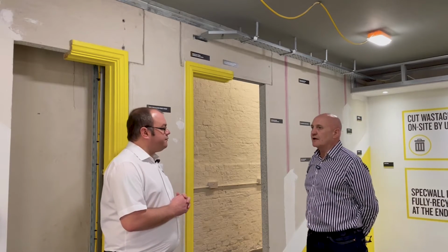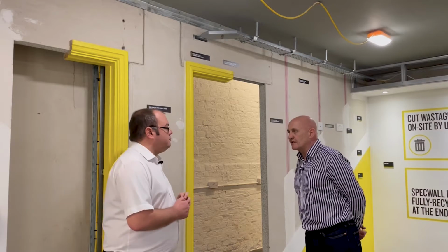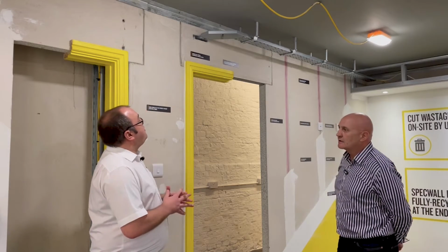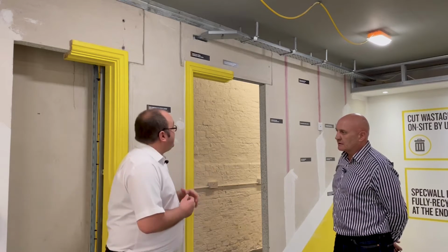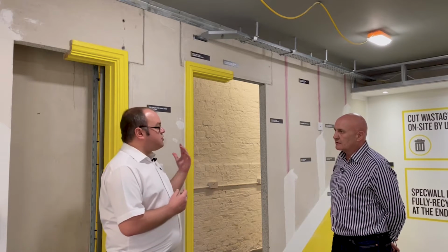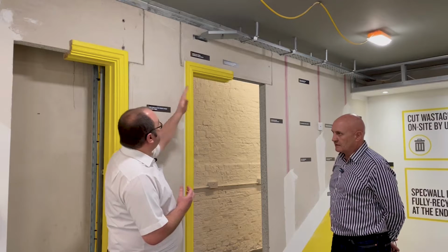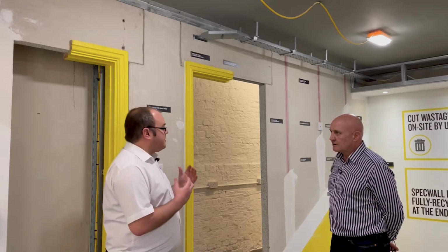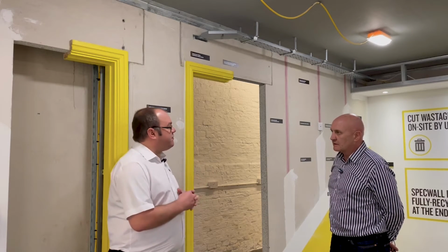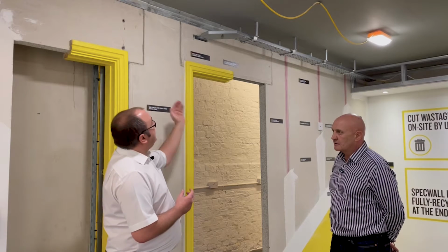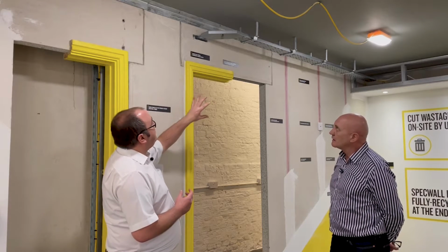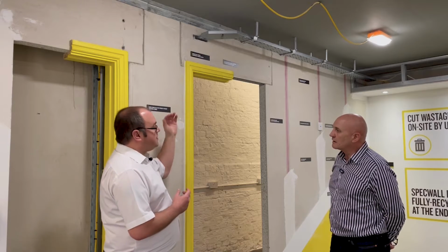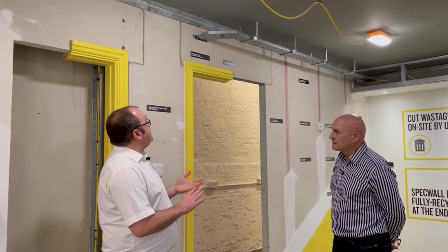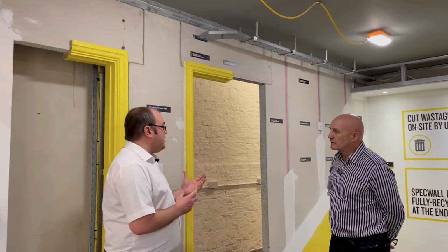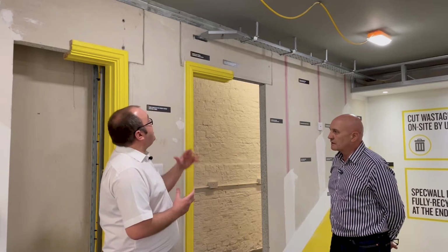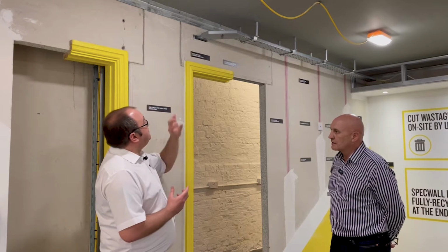Does that cover insulation as well as integrity? Yes, the fire resistance test we have to conduct covers both integrity, which is stopping the fire getting from one side of the wall to the other, and the main factor of heat transfer, the insulation rating. With this detail, if you simply had a Pattress Fireback on both sides of the wall with an annulus of HPE sealant, that's going to provide a fire rating of E120, that's 2 hours integrity, and it will also achieve the insulation rating for 60 minutes.